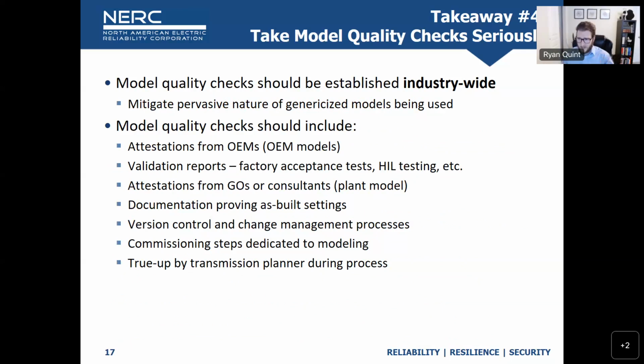We need to know that the model matches what's out there in the field. That could involve things like attestations from the OEMs, validation reports from the OEMs, factory acceptance tests, hardware-in-the-loop testing, attestations from the generator owner and/or the consultant regarding how that plant model was put together, documentation of as-built settings, some type of change management process or version control, commissioning activities dedicated to modeling, and that true-up activity that really needs to take place during the commissioning process with the transmission planner or planning individual or organization present and involved—which, as we hear pretty widely around the industry, is not the case today. But it was the case many years ago, when we weren't connecting hundreds of plants in one year. We were connecting a small handful, a dozen or a couple, something like that.